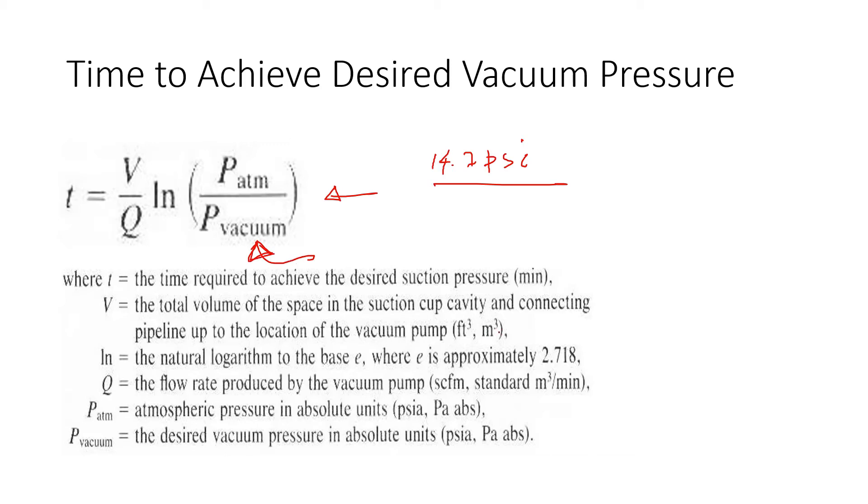Now, another thing you must be careful about is V is the volume all the way from the vacuum pump to the object that is being lifted by suction. So it's the total volume, pipings, valves, the area right under the cup. And so all of this volume is V.